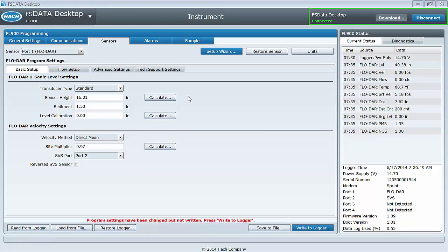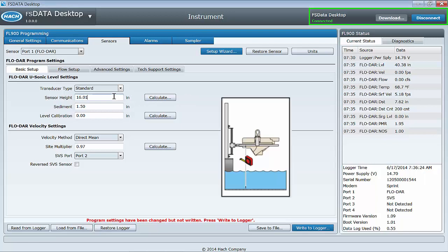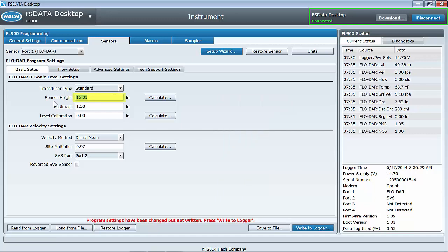Method 2: Measure the sensor height, which is from the base of the frame to the bottom of the channel, and input the value measured into the field here, and then write to logger.